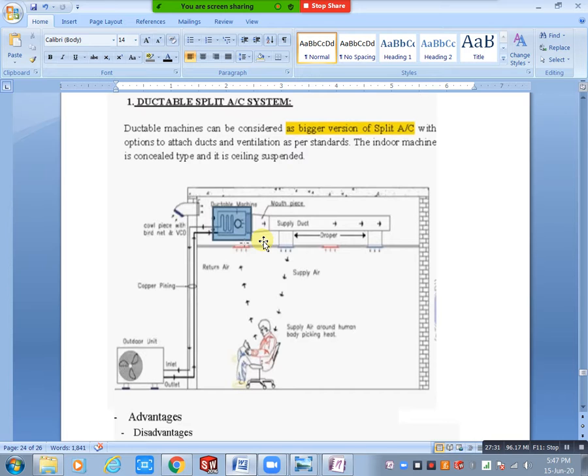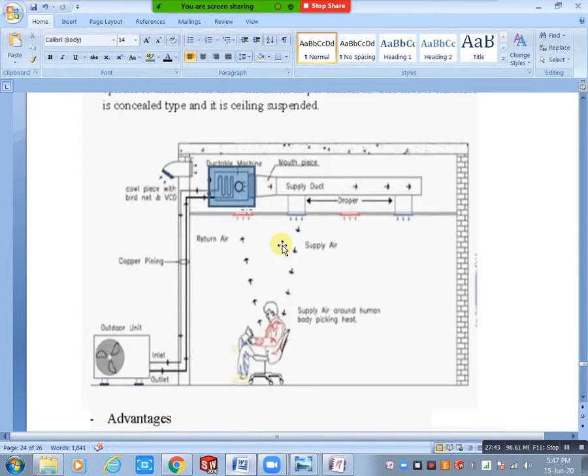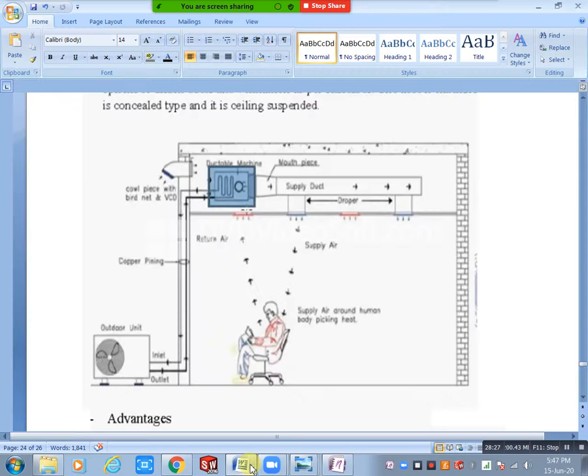This image shows an FCU or AHU — air handling unit. This is a ceiling suspended unit (CSU), also called ceiling suspended AHU. Here we can see hangers. The two openings are supply purpose. For return air, it is from the back side. Ducts are directly connected to the supply openings. For drain pipe, you connect it here and use a U-trap — both for AHU and FCU — and connect the drain pipe to the floor drain.